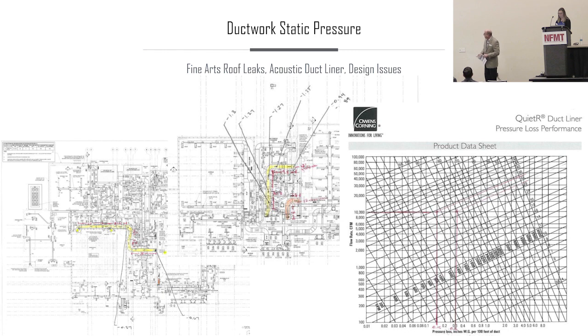What I like about this particular vignette is that it highlights one of the things we see here, as with the vignette about the two condenser water pumps: there's the design, and there's a building that's commissioned. We do new construction commissioning, and I'm going in to ensure that it is meeting the owner's requirements. But those owner's requirements, as interpreted by the engineer of record, and the sequence of operation, everything goes in accordance with the engineer, because he owns it.